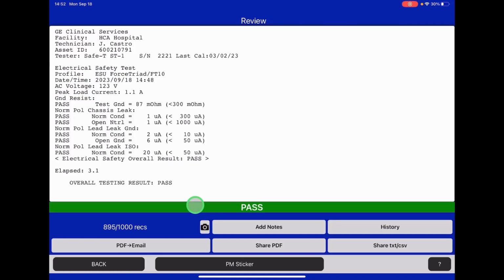And once it is done, you'll get to a review screen here, where you can see all of the information, all of the testing that we performed, including that header information I mentioned earlier, the test equipment we used, the date it was calibrated, and then all of the testing we did for electrical safety are listed down below. And in the center here are your measured values. Over to the right are your test limits per the manufacturer's requirements. We've completed this test. It passed. The app will indicate everything passed. If anything failed, the app would show fail here.